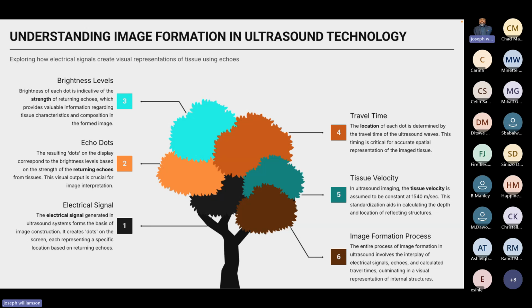can actually distort your image. There is something called an artifact, right? Artifacts in ultrasound are things that are not really there. It's kind of like when you're looking at the sun through your sunglasses and you see those rings in your sunglasses, or, a better example, you're driving at night and you look at the traffic lights and your eyes are not what they used to be and you have those rings. Those are not really there; they're artifacts. And sometimes artifacts end up on our images because of travel time.